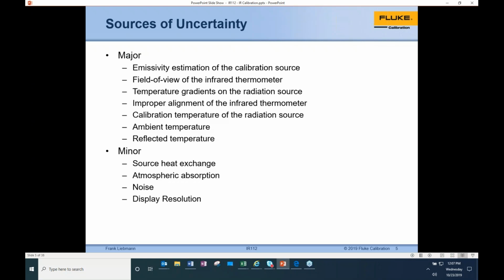Some of the minor sources, source heat exchange, usually that's if you've got the unit set up against where there's a fan or there's something else that can affect or add to the stability. So again, if you had your heat source set up under, say, a vent in the ceiling, you could potentially have some problems there. Atmospheric absorption is another one. We'll show an example of that. And then just noise. Noise usually can be reduced using a partition or making sure you've got a good distance to spot size ratio, and then to just your display resolution.